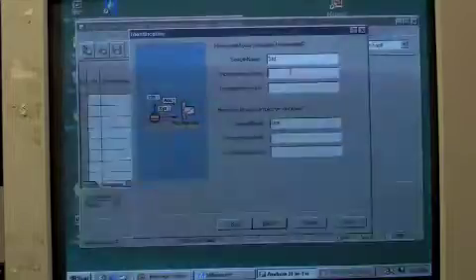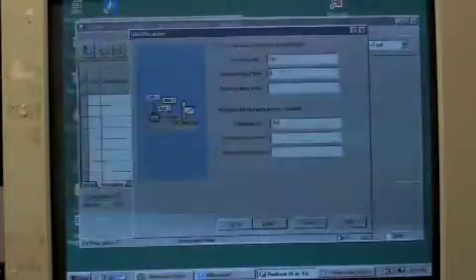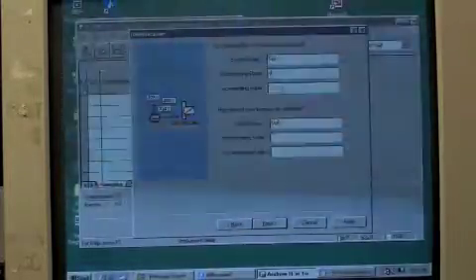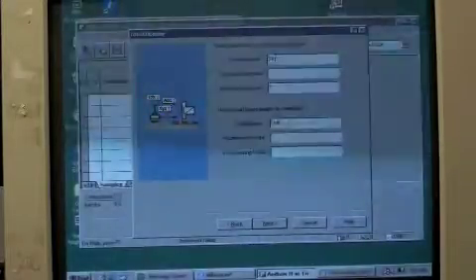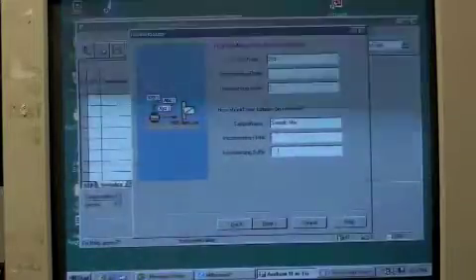This is where you can name the samples. The standards are called 'standard.' With a prefix, you can put a letter or number at the front — for example, if you put 'a,' the next run would be 'b,' then 'c.' Suffix is a lot more useful; here we'll put '1,' so when the standard is run more than once it'll be called number two, three, and so on. The sample name we'll call 'mix,' for example. Since we're only running one sample, we don't need to put in a suffix.